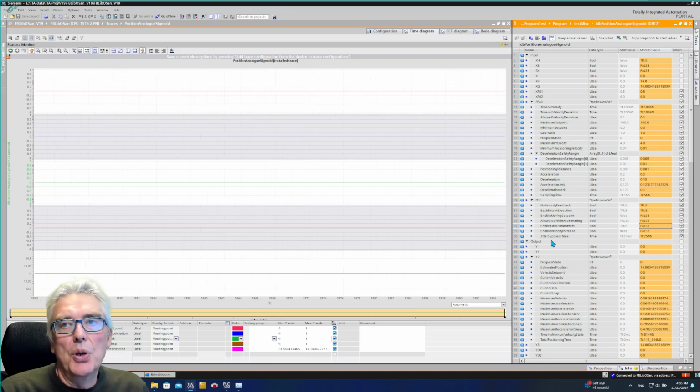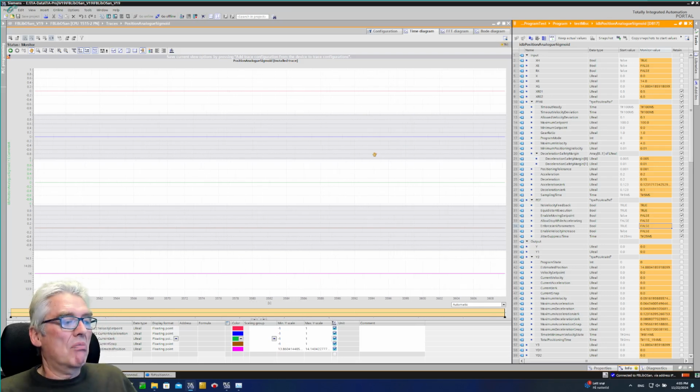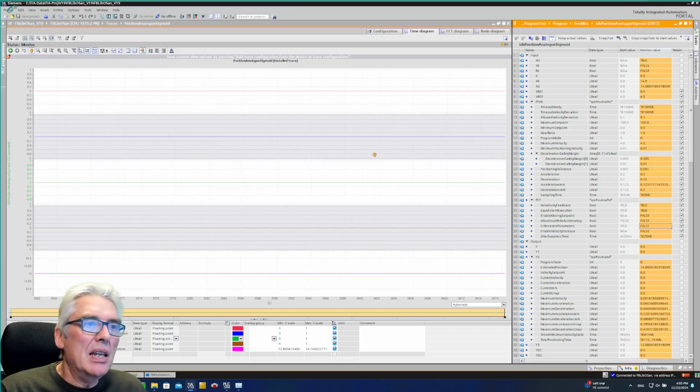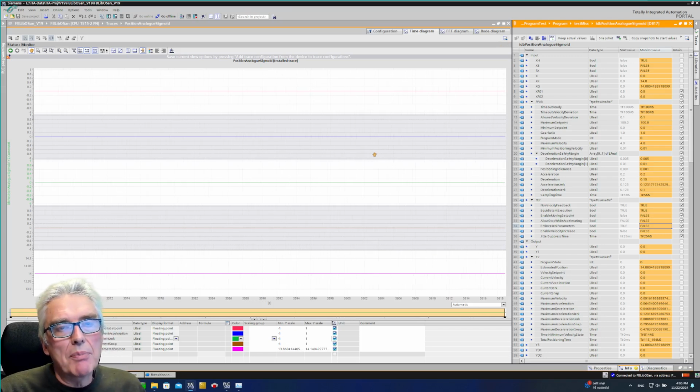Because what you would do is just estimate: the homing switch is here, and if I'm doing homing at this speed, I should probably start to decelerate and move at the minimum speed until I hit the homing switch and just stop. So that's what you would do. So this is just a workhorse, let's say a motion profile or program. Because these instructions that PLC Open specifies are instructions like move absolute, move relative, and so on.